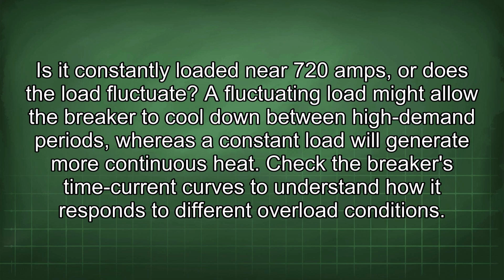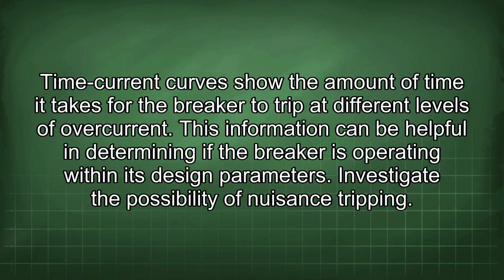A fluctuating load might allow the breaker to cool down between high demand periods, whereas a constant load will generate more continuous heat. Check the breaker's time current curves to understand how it responds to different overload conditions. Time current curves show the amount of time it takes for the breaker to trip at different levels of overcurrent. This information can be helpful in determining if the breaker is operating within its design parameters.